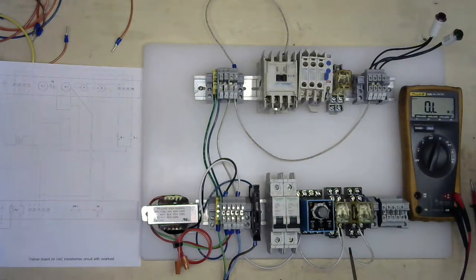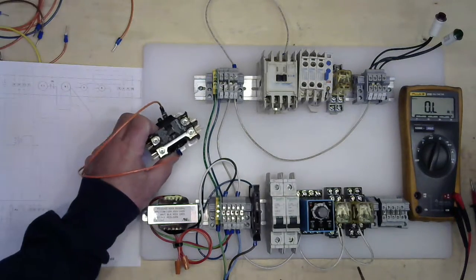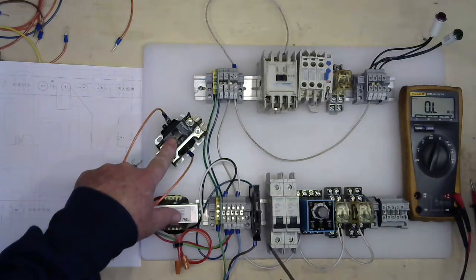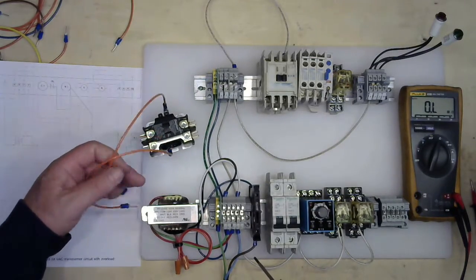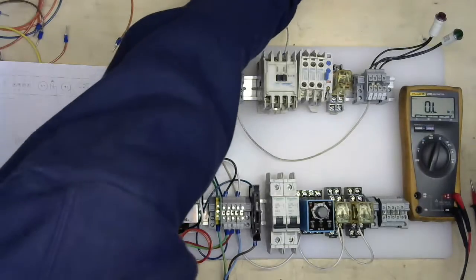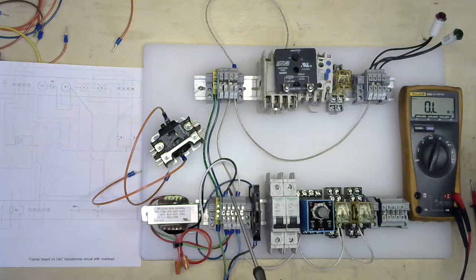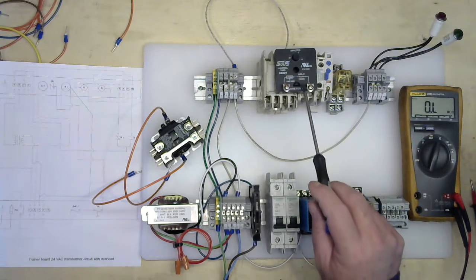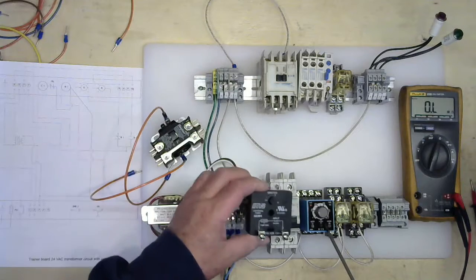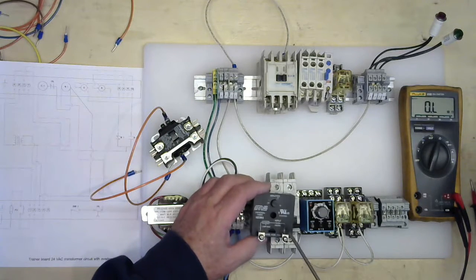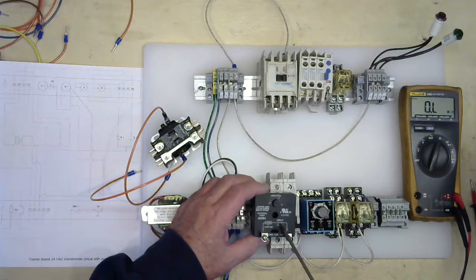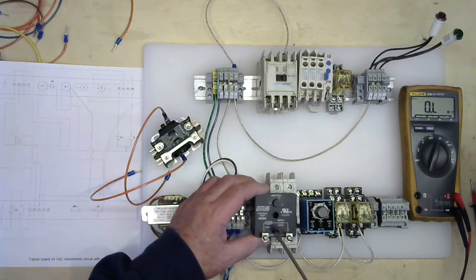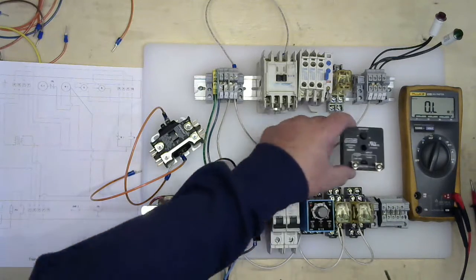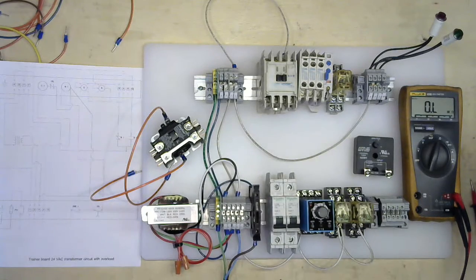For the sake of the contactor, we're going to introduce a magnetic contactor. I've already had the connection points for those. And we're going to utilize a 24 volt time delay on make relay. This one is different from this, where this one does not need a coil to start timing out. Once the input voltage is applied, our timer is set, and the load on here will energize, allowing the transfer.